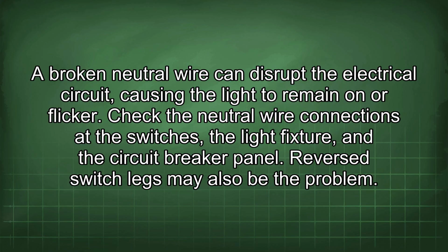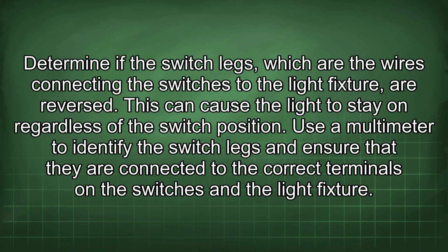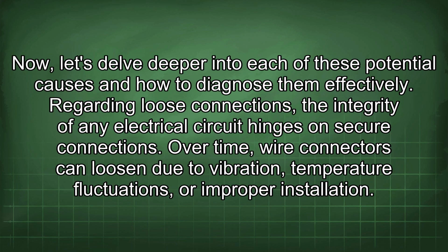Reverse switch legs may also be the problem. Determine if the switch legs, which are the wires connecting the switches to the light fixture, are reversed. This can cause the light to stay on regardless of the switch position. Use a multimeter to identify the switch legs and ensure that they are connected to the correct terminals in the switches and the light fixture. Now, let's delve deeper into each of these potential causes and how to diagnose them effectively.